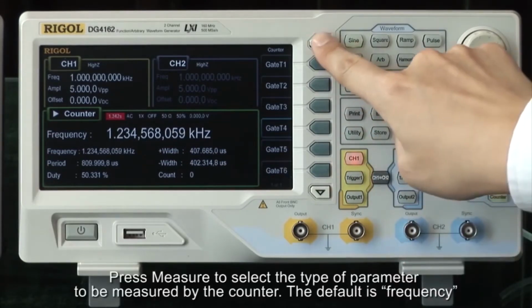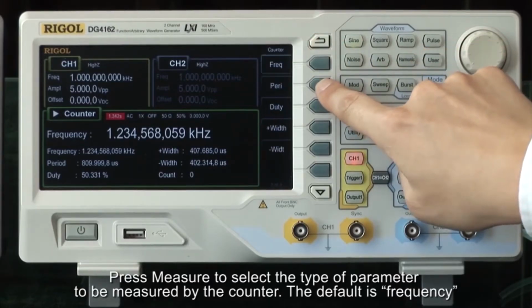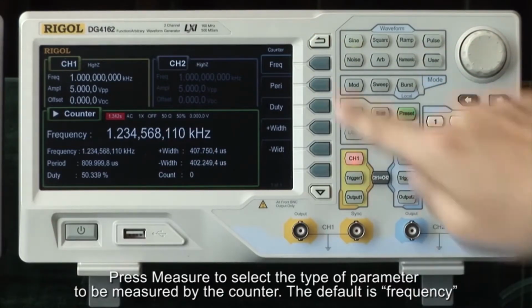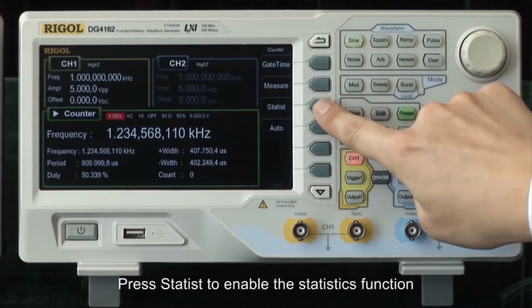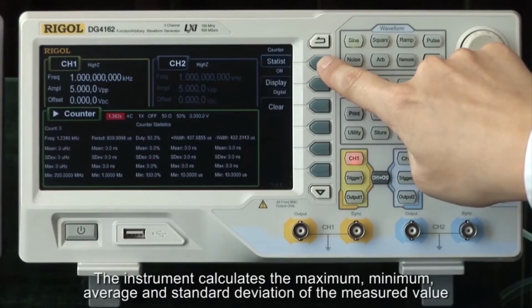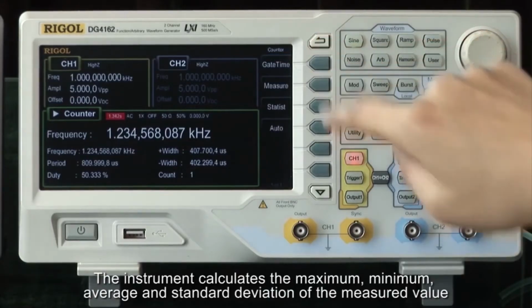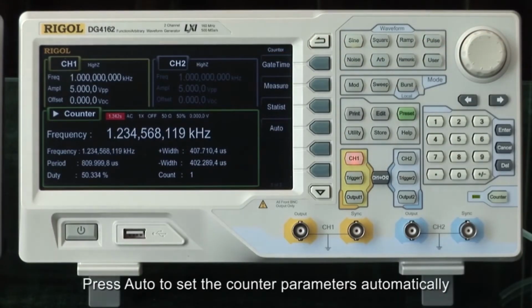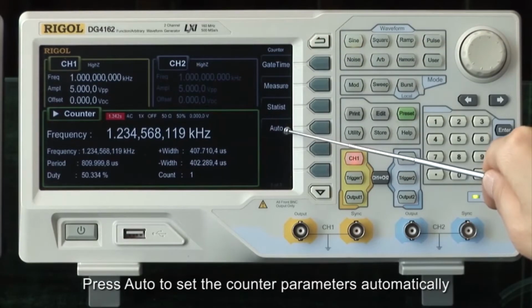Press Measure to select the type of parameter to be measured by the counter. The default is frequency. Press Statist to enable the statistics function. The instrument calculates the maximum, minimum, average, and standard deviation of the measured value. Press Auto to set the counter parameters automatically.